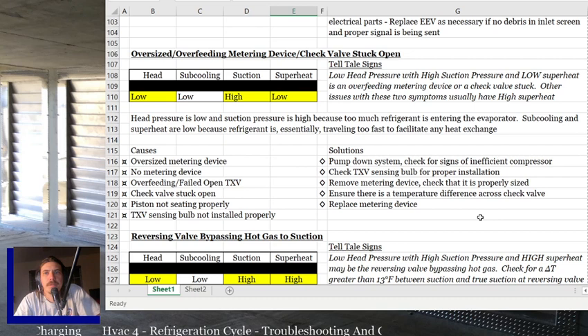So the causes can be oversized metering device, no metering device, overfeeding or failed open TXV, which does happen sometimes, check valve stuck open, piston not seating properly, or the TXV sensing bulb. Probably the most common way you'll see this issue is somebody didn't mount the TXV sensing bulb right, and so it's reading a higher heat than it should. Anytime you need that TXV to feed more refrigerant, you hold that sensing bulb in your hand, right, and warm it up. So if that sensing bulb gets warm, it's going to feed more refrigerant. So if it's not installed properly, that TXV is going to overfeed.